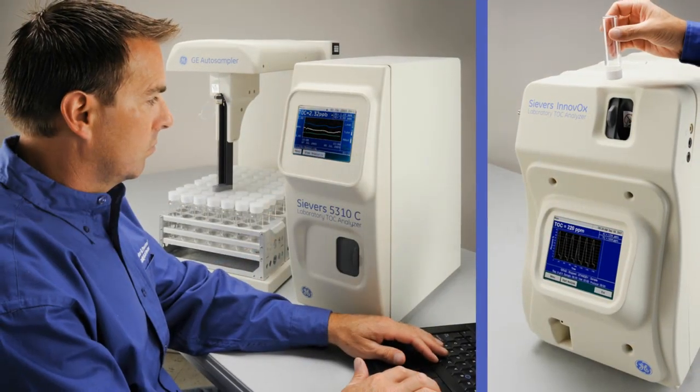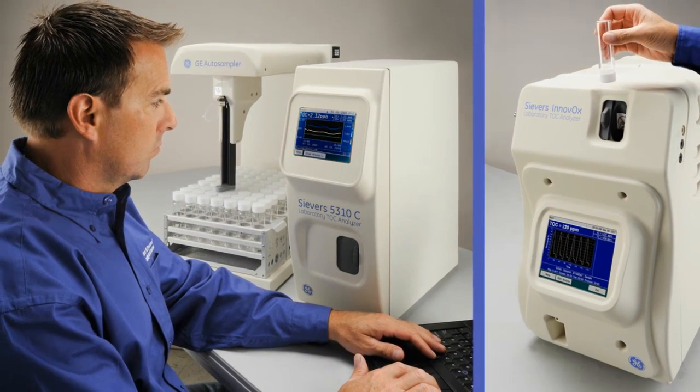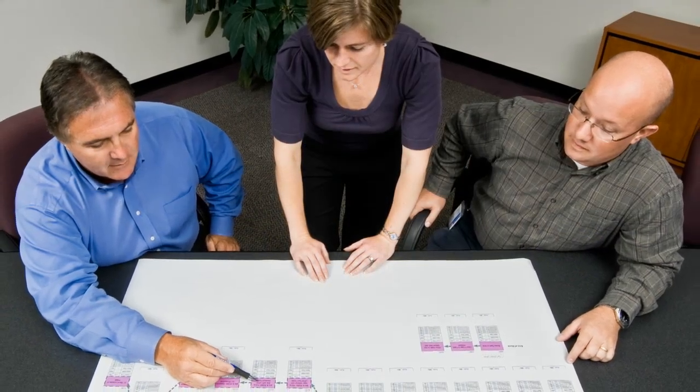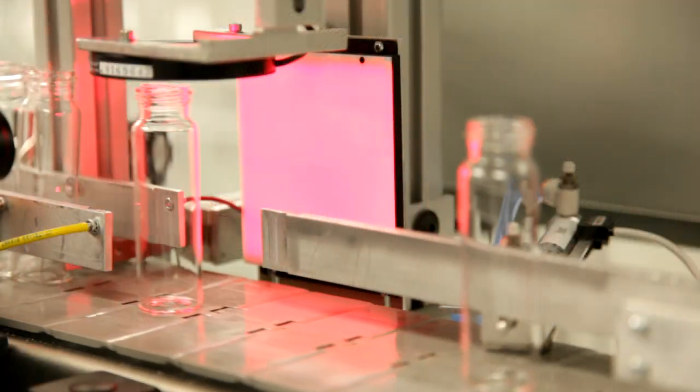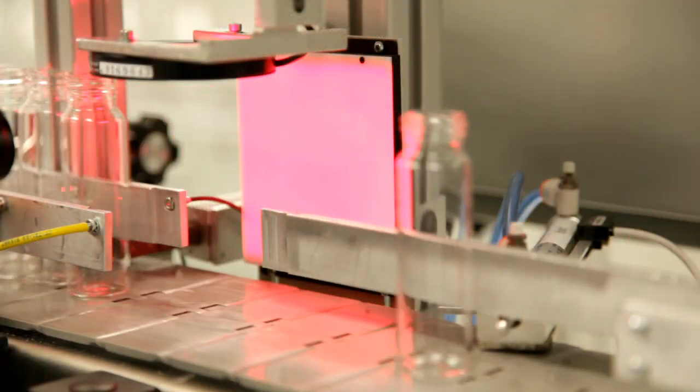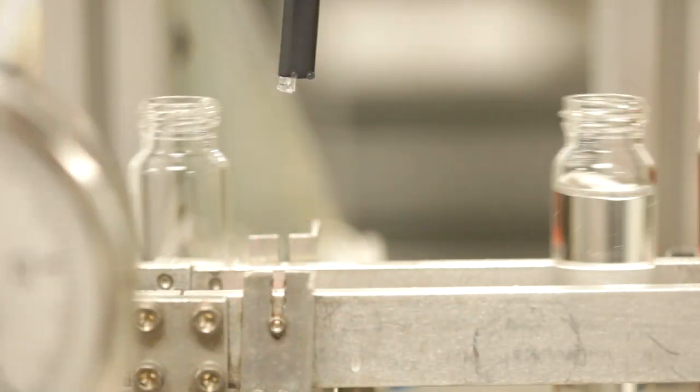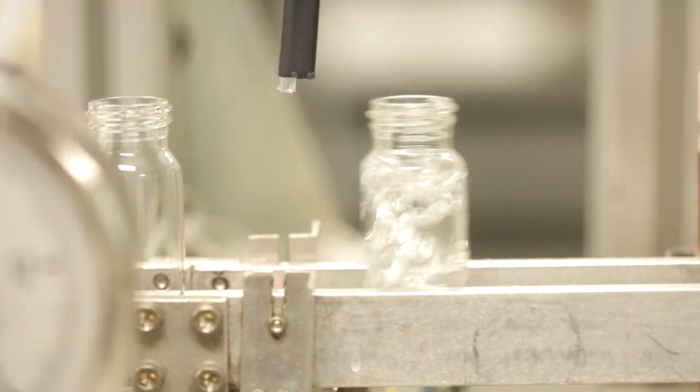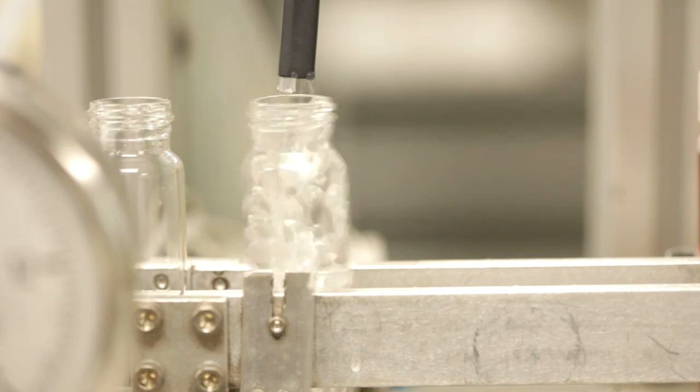Our TOC standards give you confidence in your TOC measurements for many reasons. First, we produce them using Six Sigma methodology and in accordance with ISO and all major pharmaceutical regulations. They are prepared from the highest purity raw materials available and are traceable to the USP.